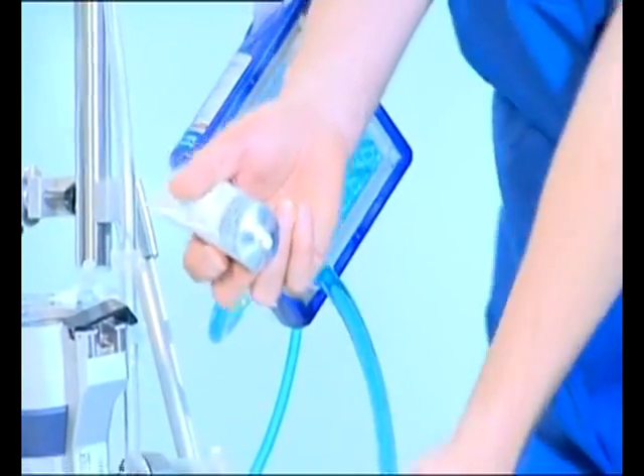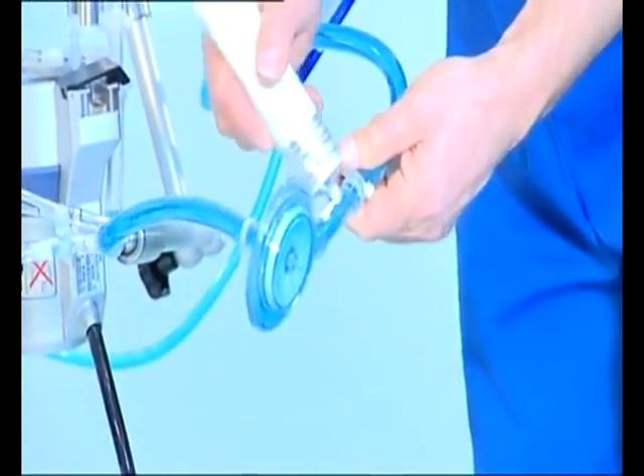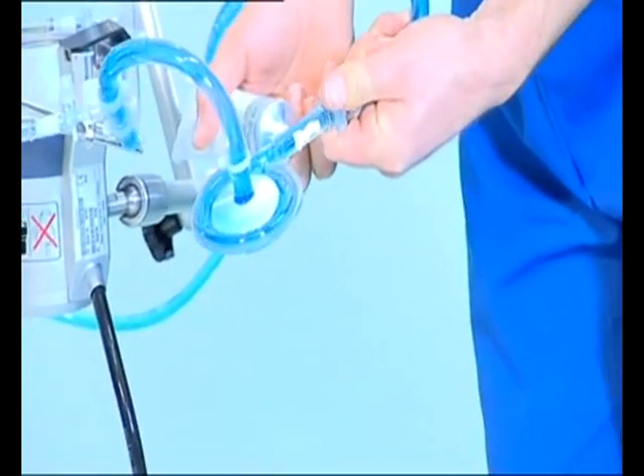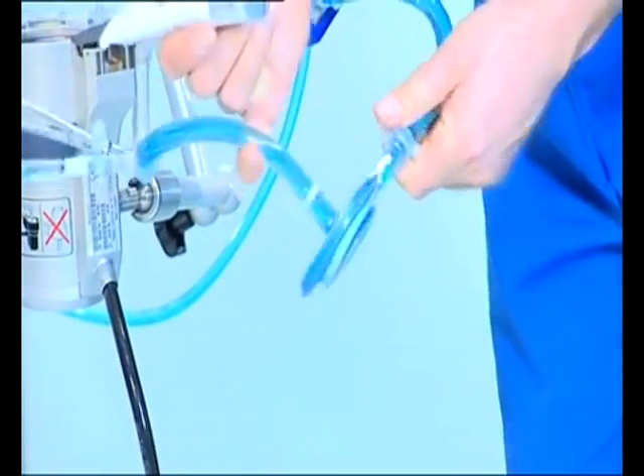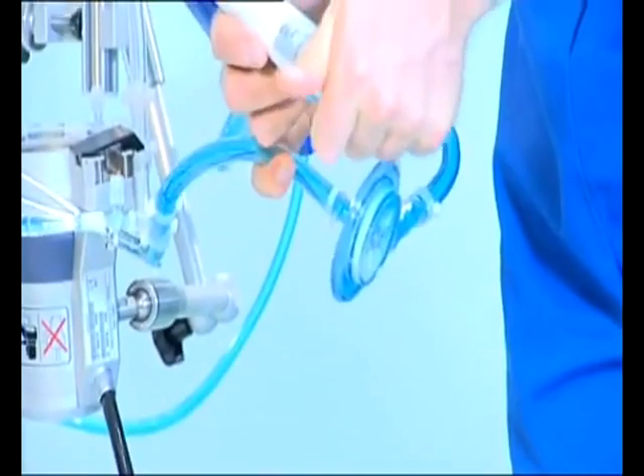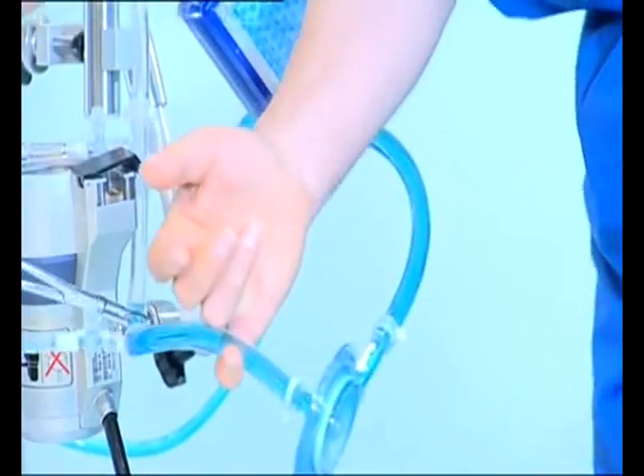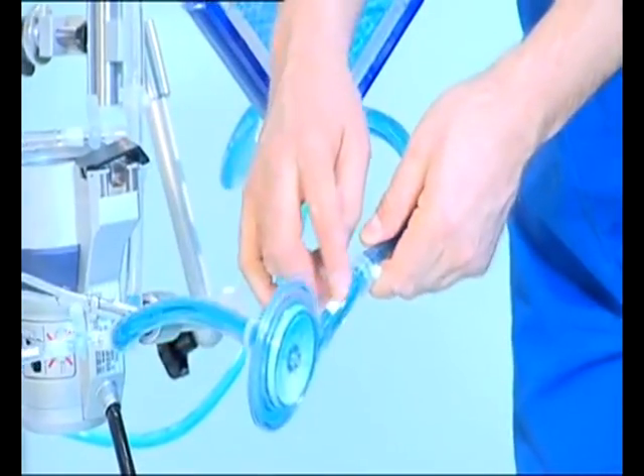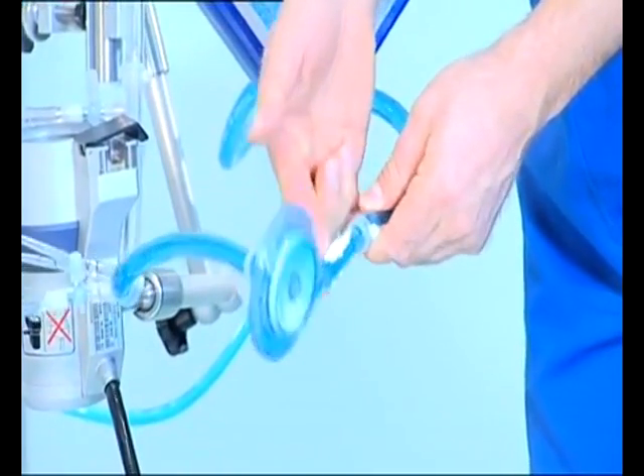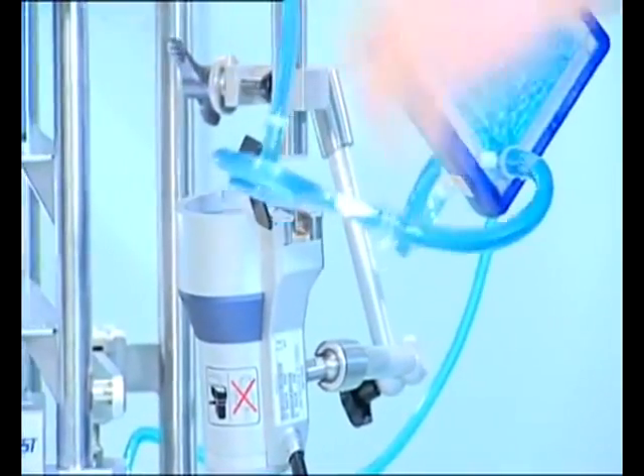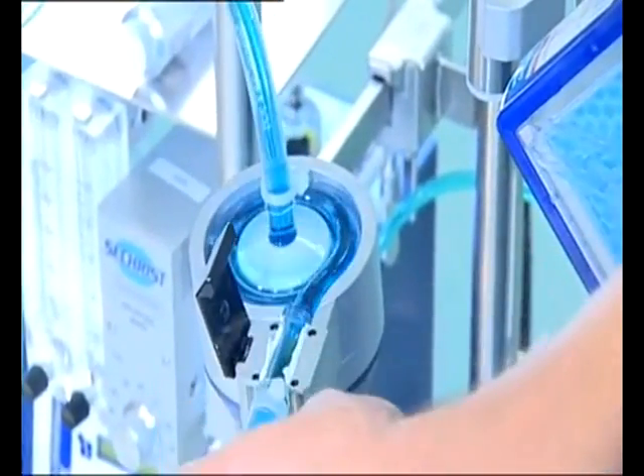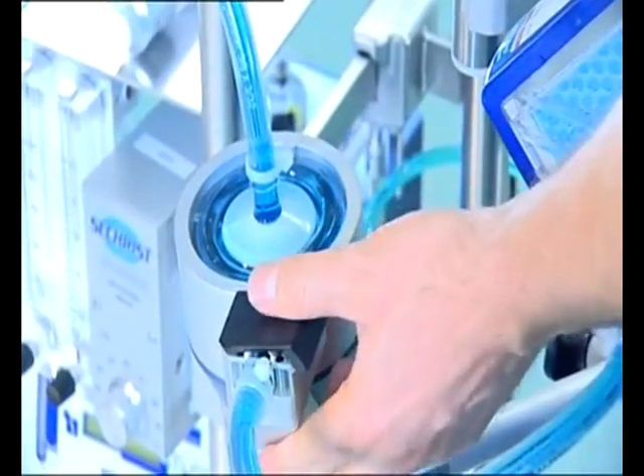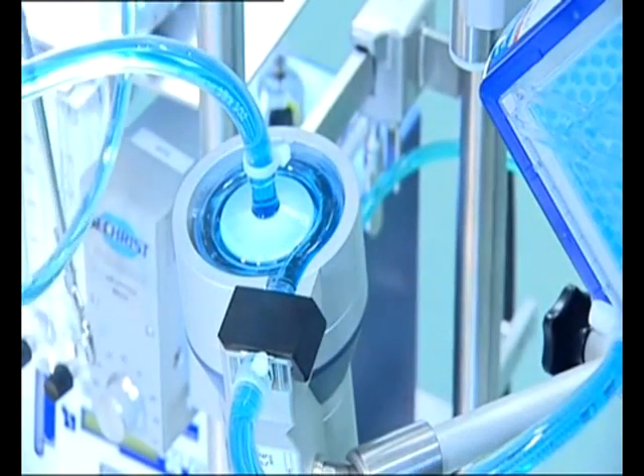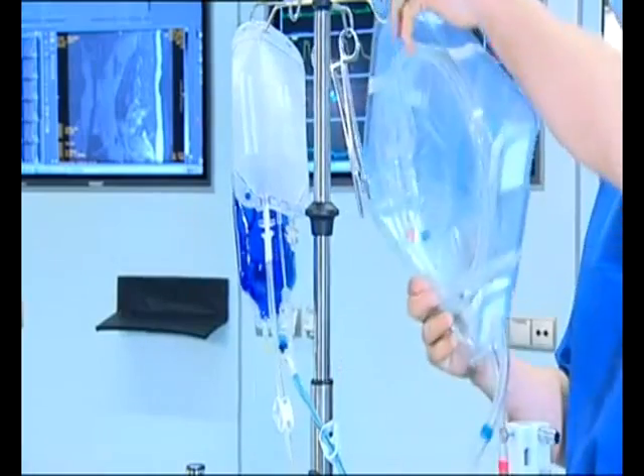The centrifugal pump and the oxygenator are now primed, and the Rotaflow can be placed into the drive unit. The pump drive outlet socket, where blood flow is measured ultrasonically, must be filled appropriately with contact gel to ensure maximum contact between the pump head outlet and the flow sensor. With the pump head placed correctly into the drive unit, the black safety flap is snapped shut. The sterile lines in the box must now be primed.